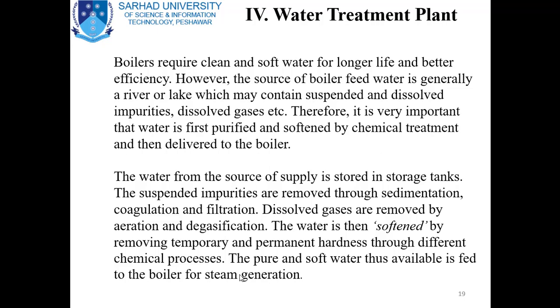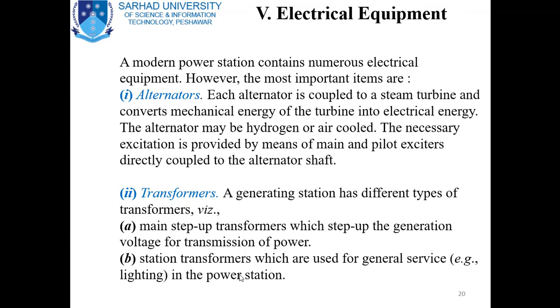The last constituent is electrical equipment. A modern power station contains numerous electrical equipment. The most important are alternators coupled to steam turbines, which convert mechanical energy of the turbine into electrical energy. Alternators are of two types: hydrogen cooled and air cooled — cooling is essential because if the alternator is not kept cool, it will stop working when it exceeds its threshold temperature. The necessary excitation is provided by means of an exciter and pilot exciter directly coupled to the alternator shaft.